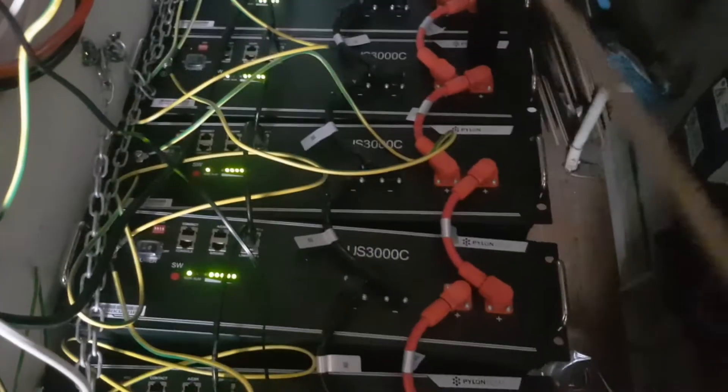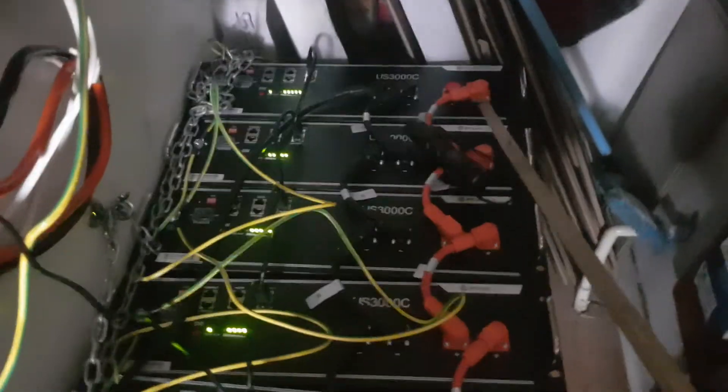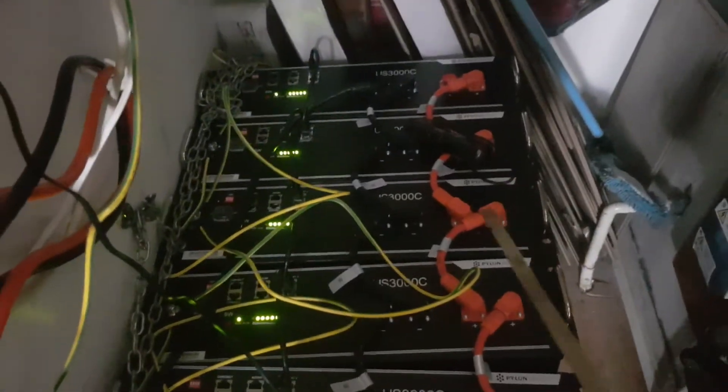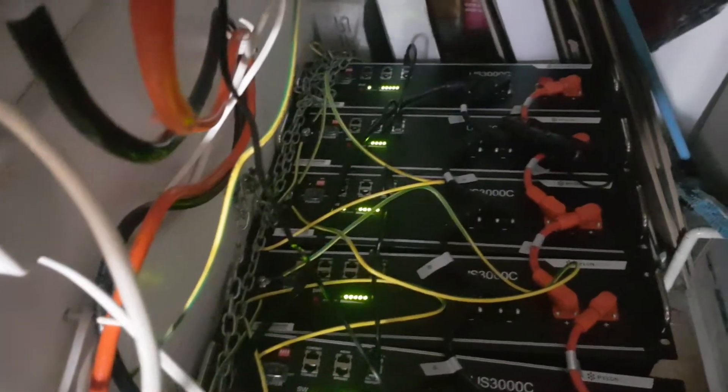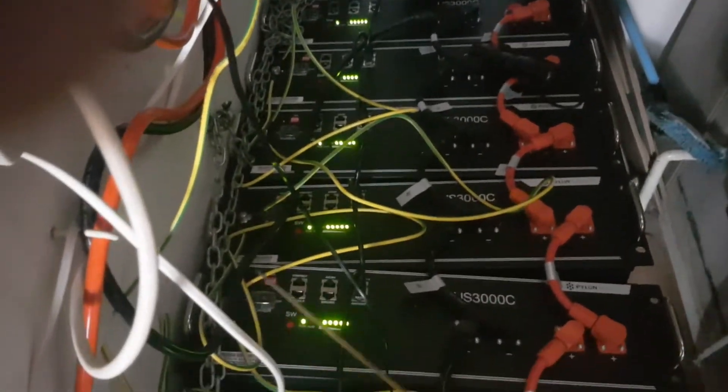What you have to do is switch all your batteries off to start with. Then you double check your connections, make sure they're all firmly plugged in. Each one, each side, you check that side and also check your earths as well. Make sure the screws are tight and check your wiring.